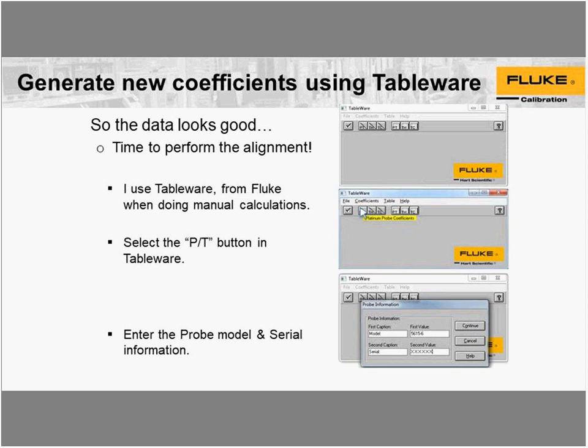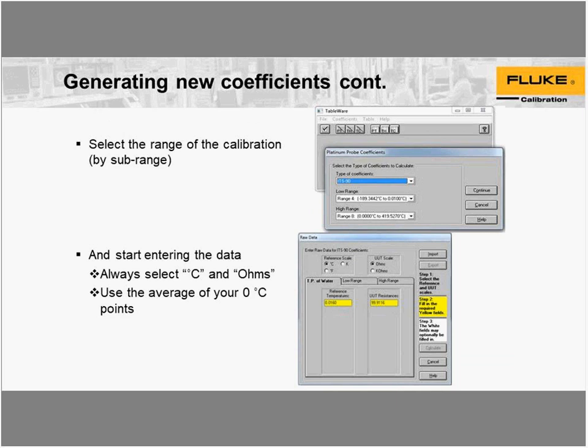What you want to do when you're using Tableware is select the PT button, which is the platinum thermometer button, on the Tableware, and then enter your probe model and serial information. And then you want to select that sub-range that we talked about earlier, and we're going to have sub-range 4, sub-range 8. Once we have selected that, we go over to the raw data entry. Then we always want to go with degrees and with ohms. Very important to do that. If you don't select those, it won't allow you to do any calculations.